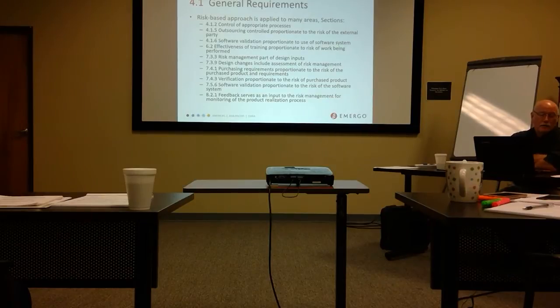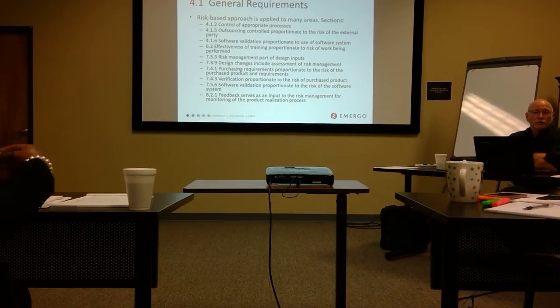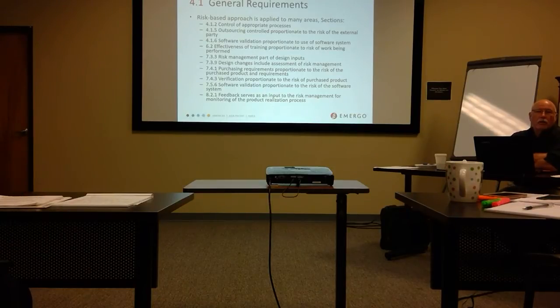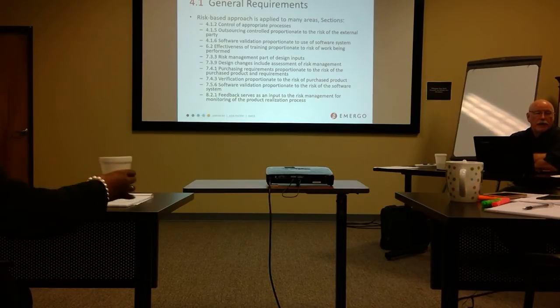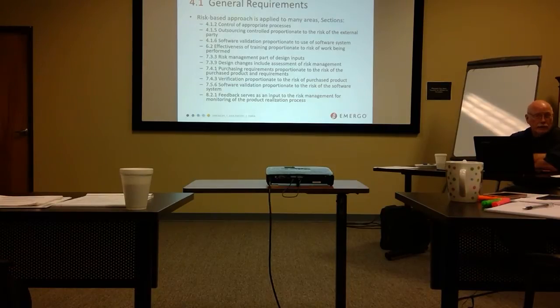This happens. In fact, this happened to me. I used to run a laboratory. We had 8 or 10 HPLCs running 24 hours a day. This is a fermentation facility. Purchasing took it upon themselves to change the grade of solvent that we needed from HPLC grade to tech grade. Well, tech grade's about half the cost. Unfortunately, if you feed that to an HPLC, it will roll over and die. So when it came in, we said, look at this, it's tech grade, send it back. Called the purchasing folks. That was the last time they did that because they almost got fired over it.